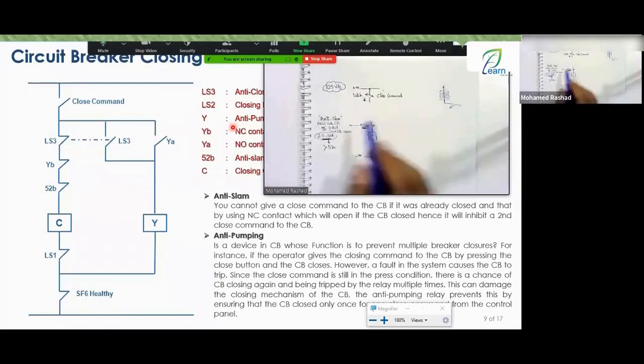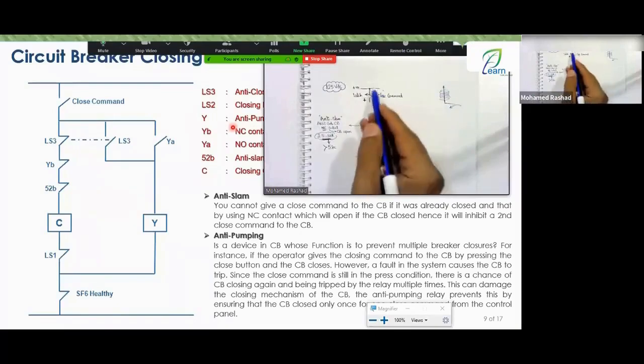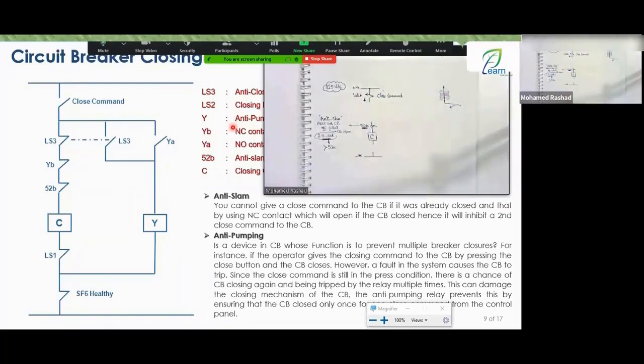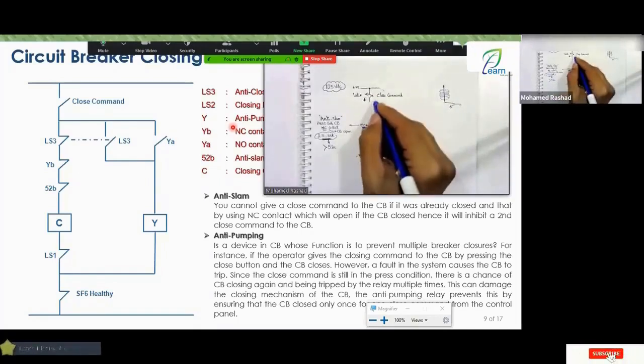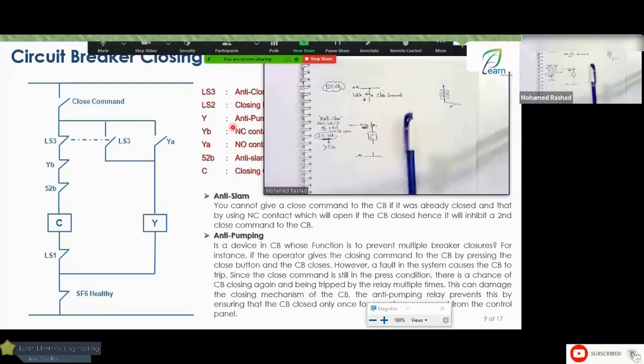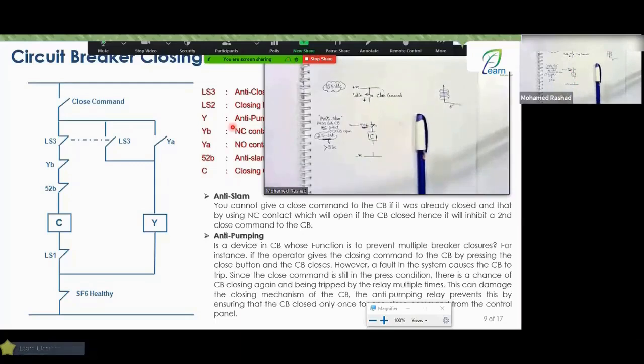Do you have a problem? No, I don't have a problem. Why? Because this contact is open, so there's no DC going to the closing coil. But if this breaker opened due to a fault or whatever reason, as soon as it opens, this contact returns to normally what? Normally closed. So as soon as it returns to normally closed, it finds the positive again, and it closes the breaker once more. Was the breaker supposed to close? No. Okay, that's number one.